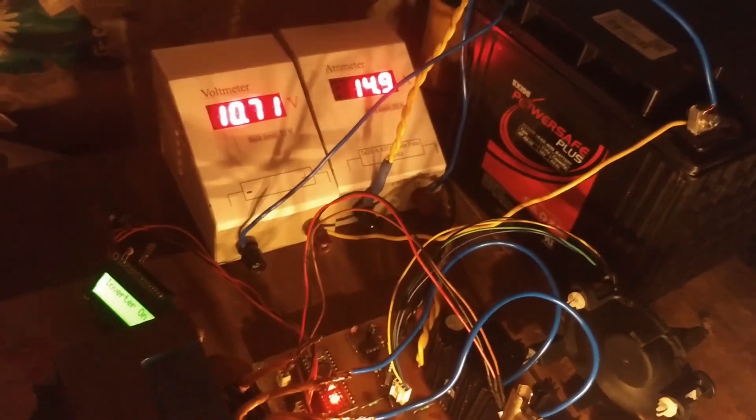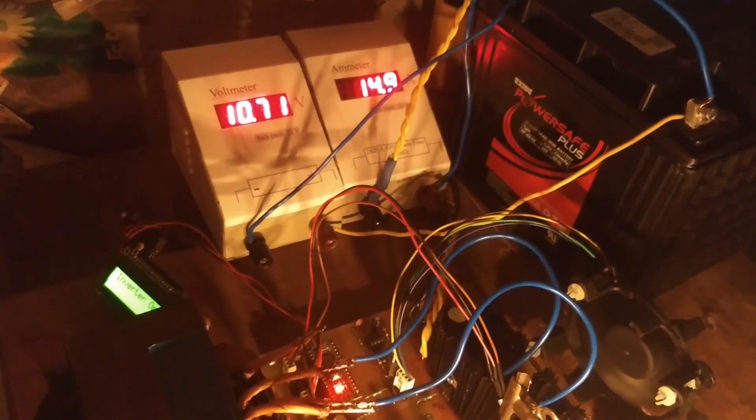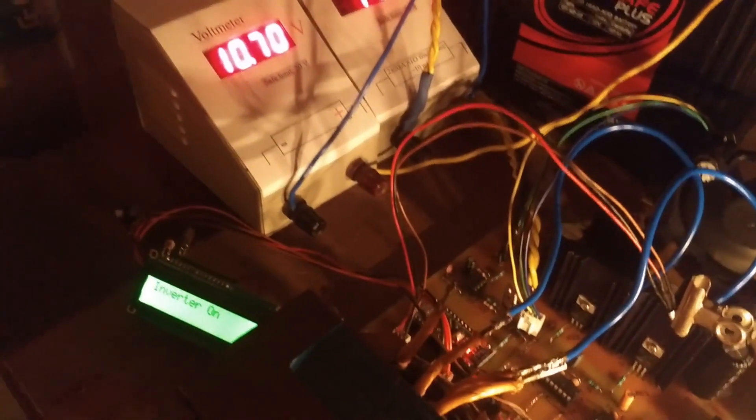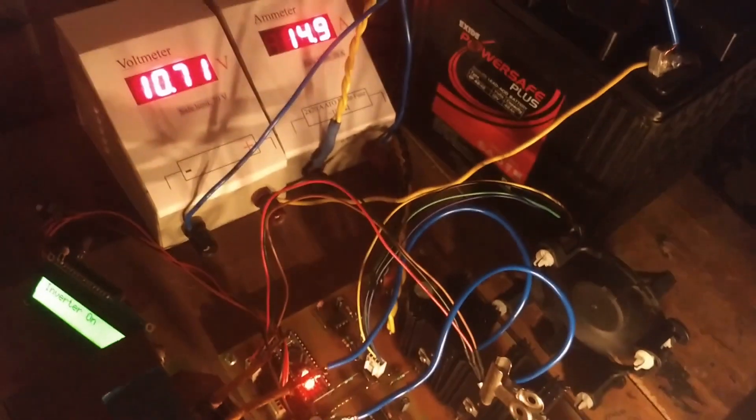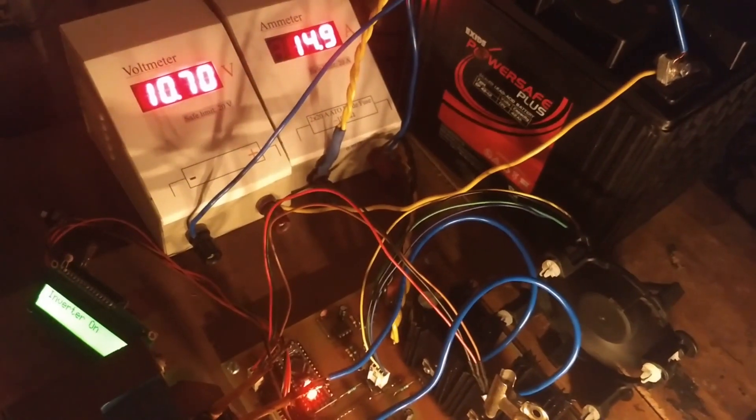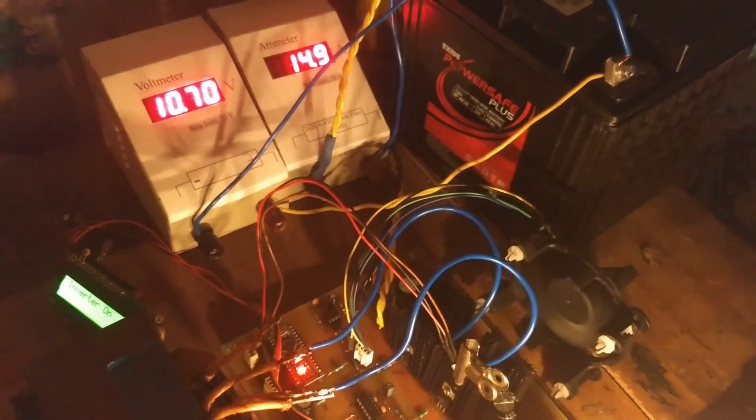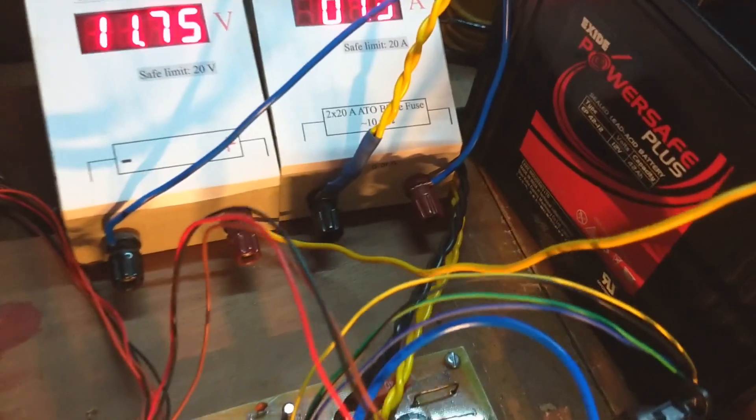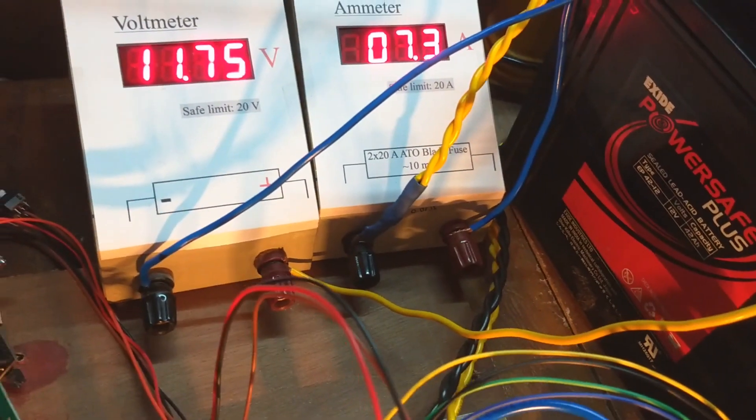It is running continuously for 3.5 hours, and the battery voltage dropped below 11V. That's why low battery beep has been started. Output voltage and waveforms are still acceptable.